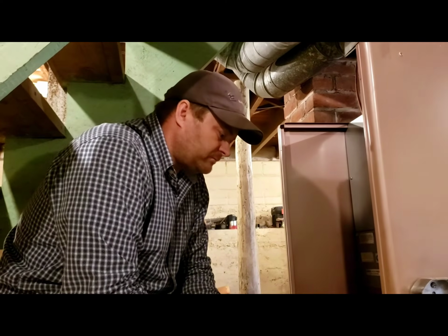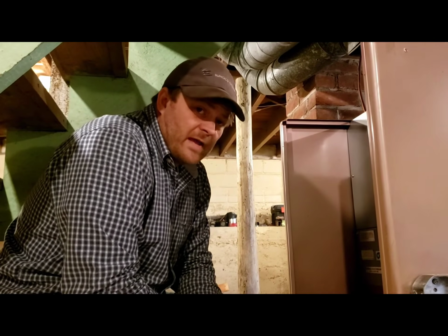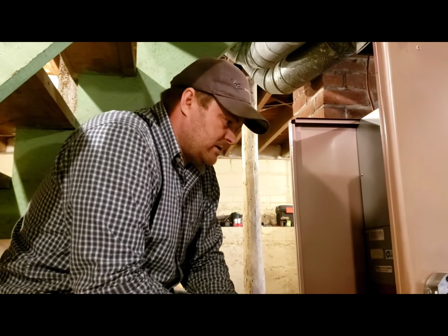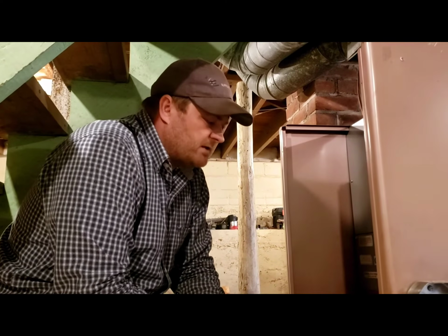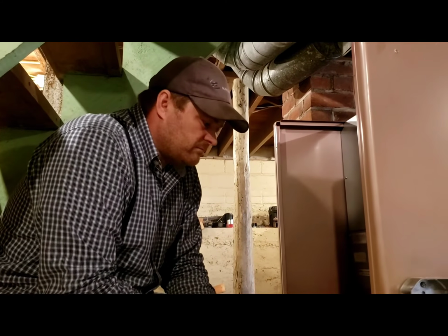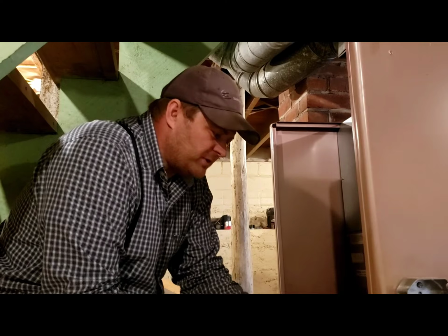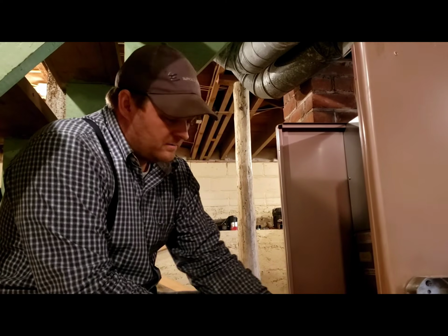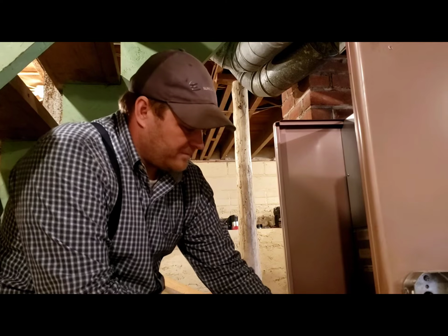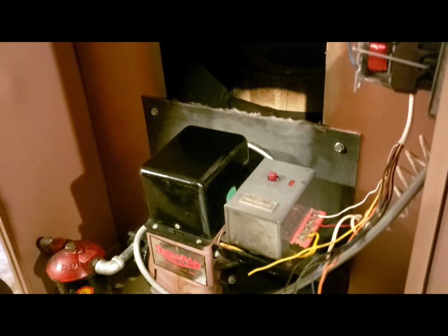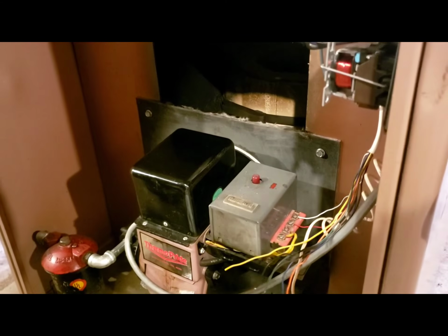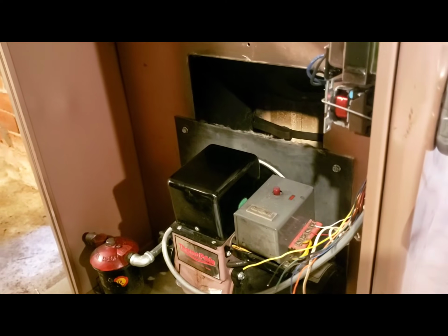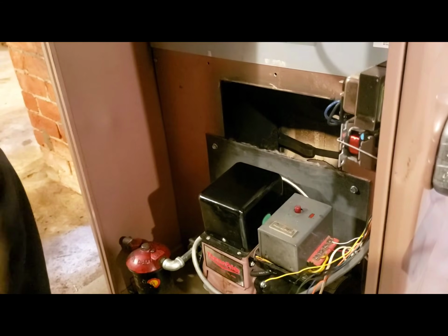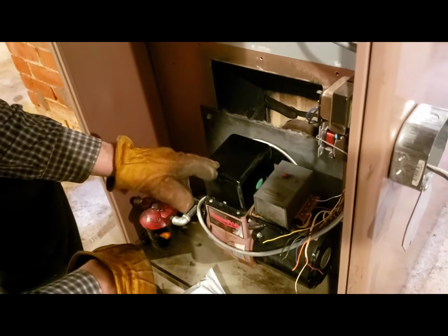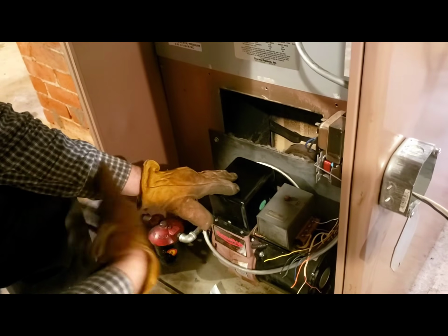Okay. And these are mostly mechanical furnaces, this brand? Mechanical. Not electronics. Oh, yeah, this one is not the digital primary, and if you have a little tiny transformer instead of this big one, I don't like those. Those don't run all the time. This transformer runs the whole time your furnace runs. So if you're in a storm, and literally a huge storm will reverse your draft and blow your flame out, that can't happen with these, because this is your electronic ignition. It's just going to keep it going no matter what.